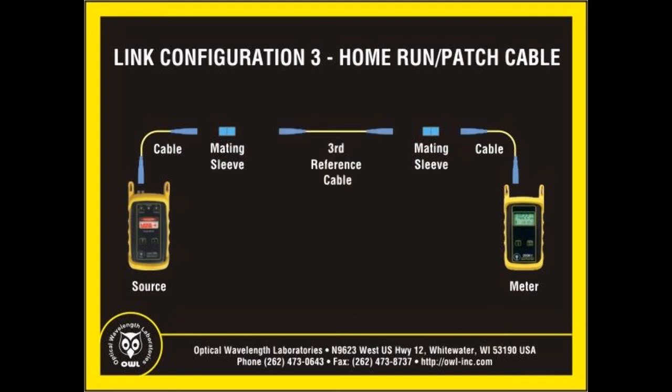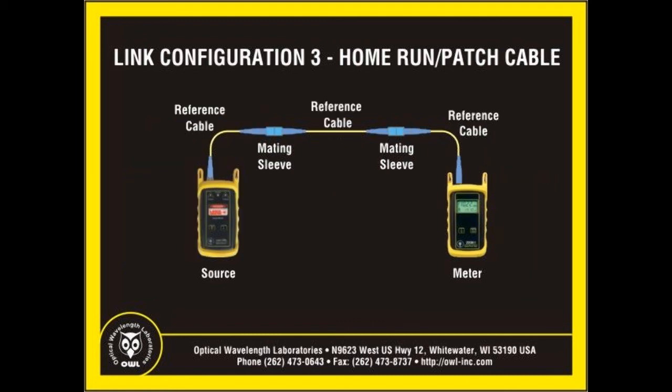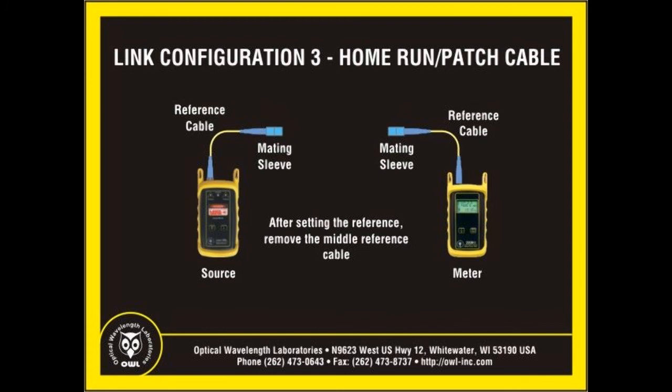Simply add a third reference cable in between the mating sleeves to connect using the three jumper method. Now you can set your reference. Once the reference has been set, remove the center patch cable and insert the home run cable or patch cable under test.